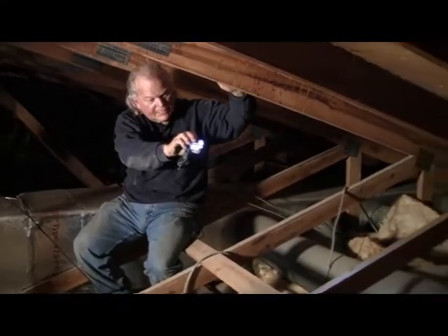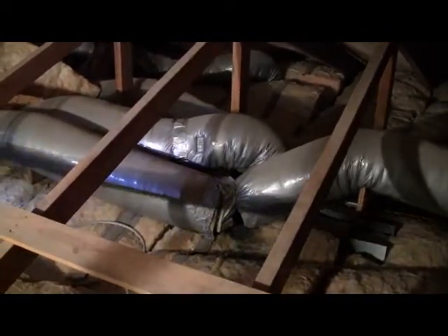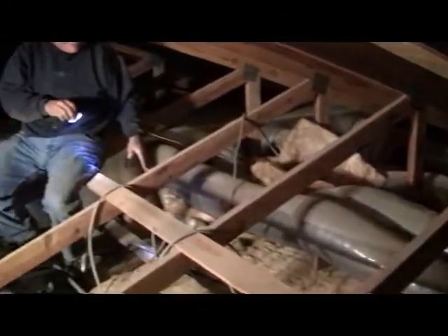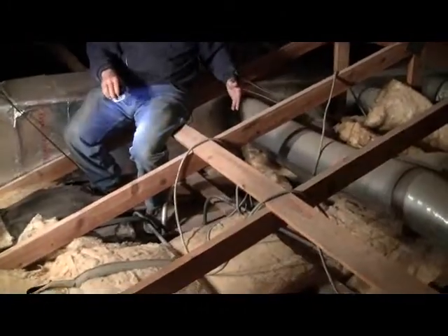As we go further back underneath this area, we're connected to wall sections that are connected directly to the attic. So this entire plenum system is a leak connected to outside. You can see right over here where I'm shining my light is the disconnected piece of flex duct that we're going to have to reconnect and seal. Now I've moved over here to the west, and I'm finding a soffit that's constructed into the ceiling below, designed to carry the cabinets in the kitchen area that's on top of the stage in the auditorium. We're actually feeling cold air being blown up into this space because of the pressure we're putting in the duct system. Let's have a closer look at this.